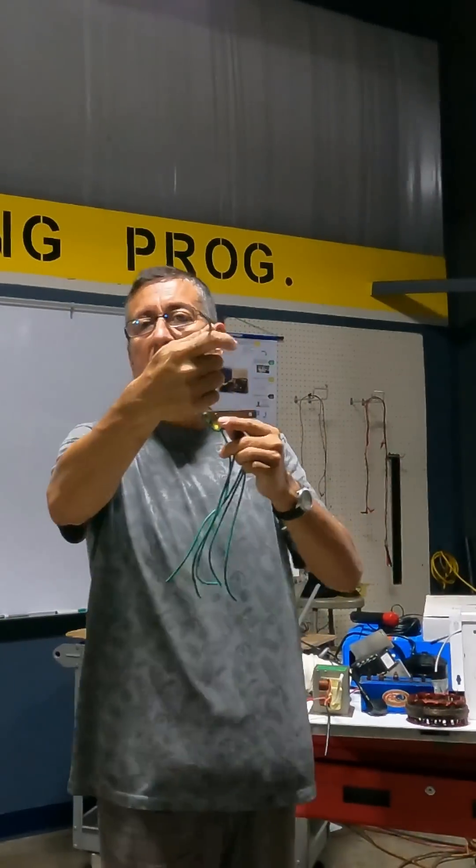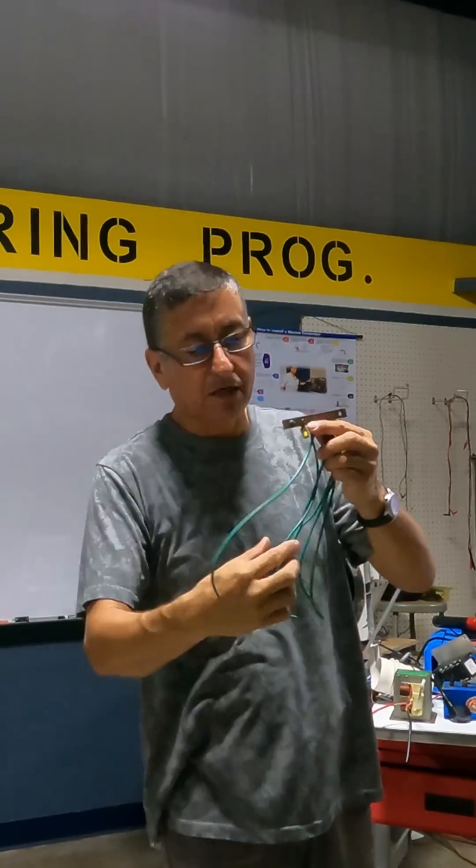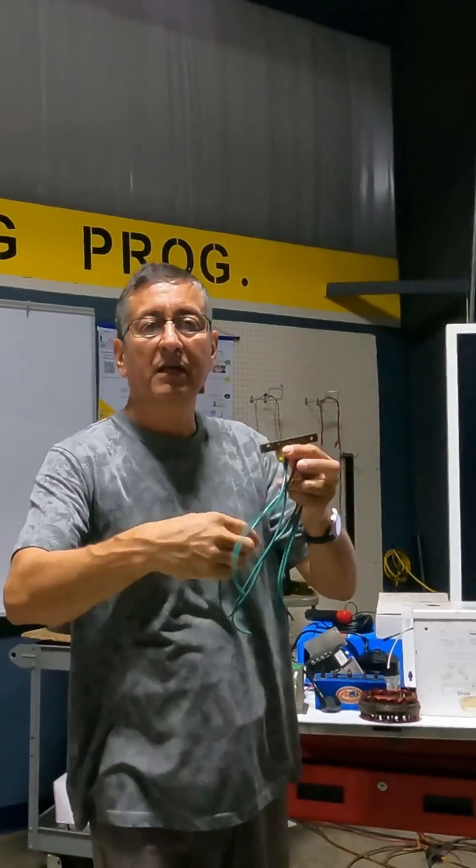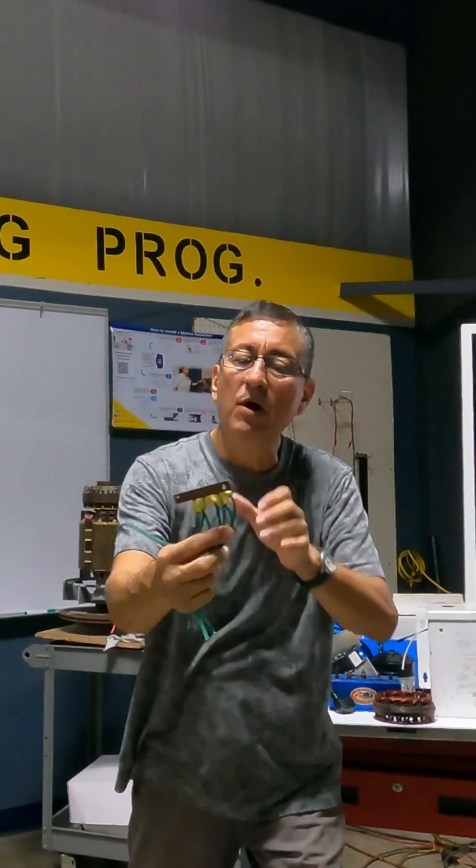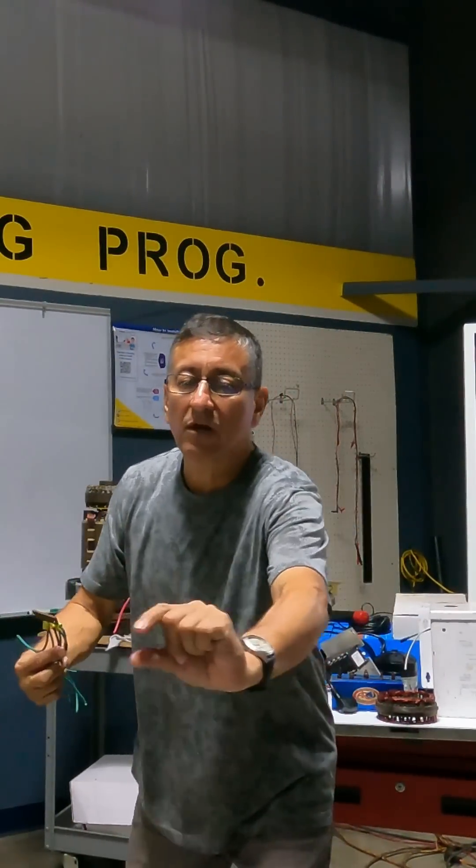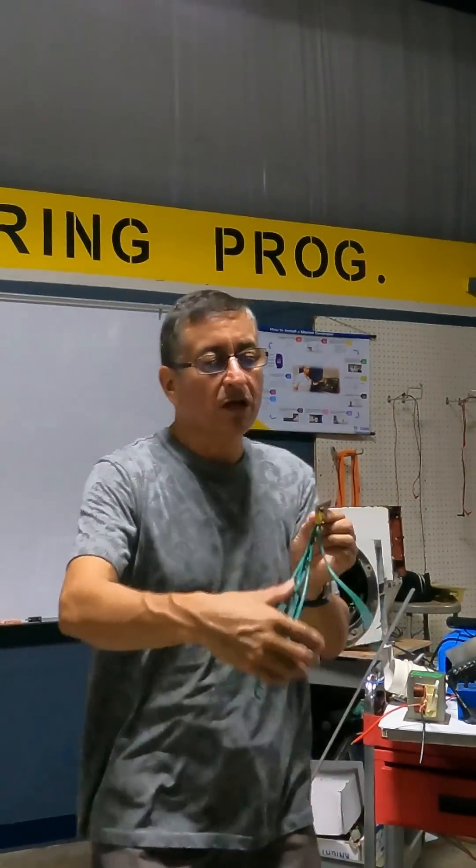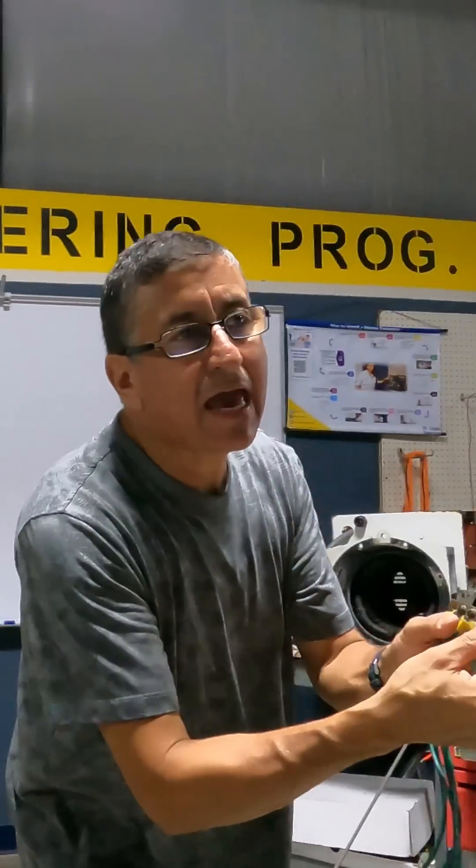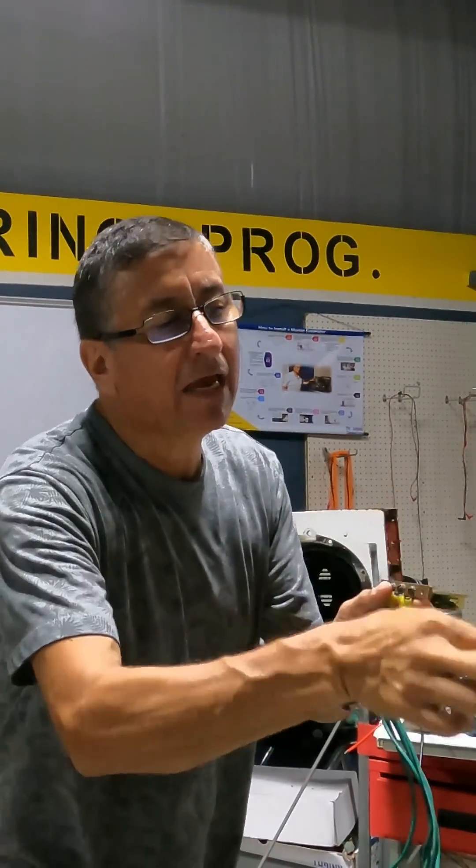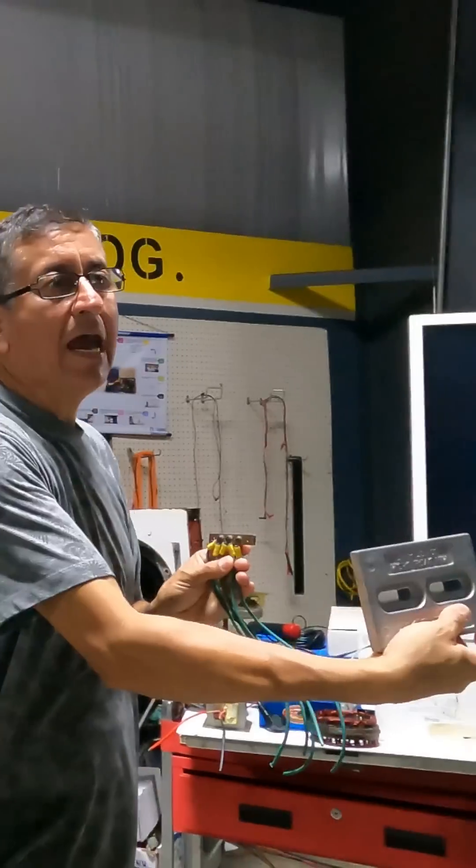And I connect the block of the water heater, the block of the fuel tank, the block of the engine with green cables. I have one of those bonding conductors on the stringer of the port side engine and another one on the stringer of the starboard side engine. This one at the end has a cable, and the cable is connected outside with the anode.